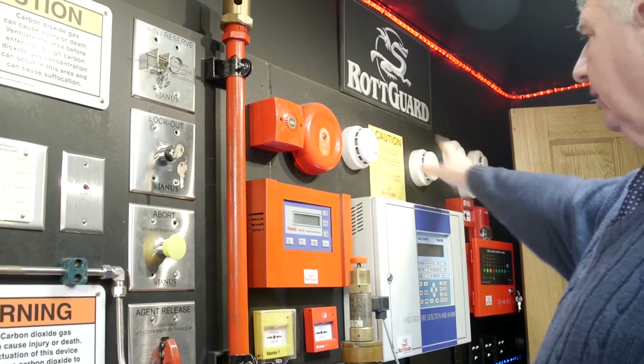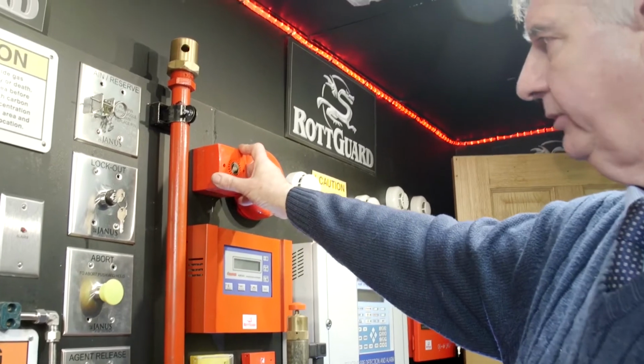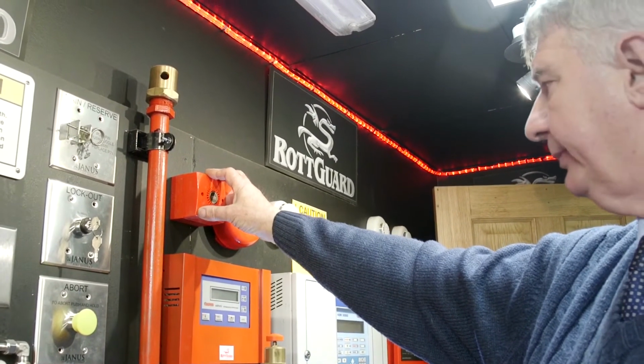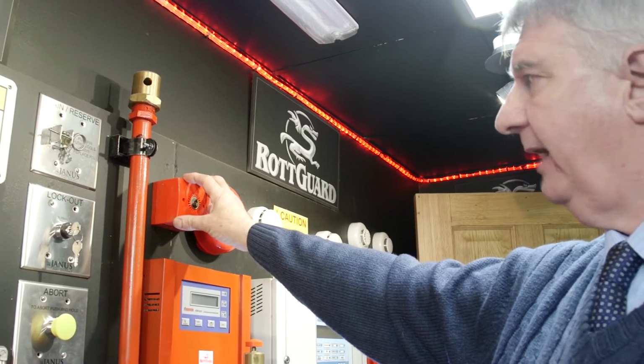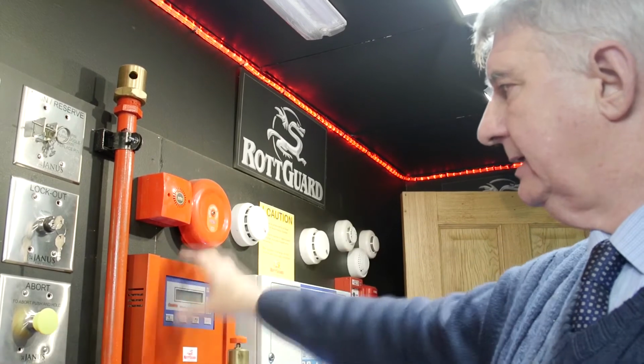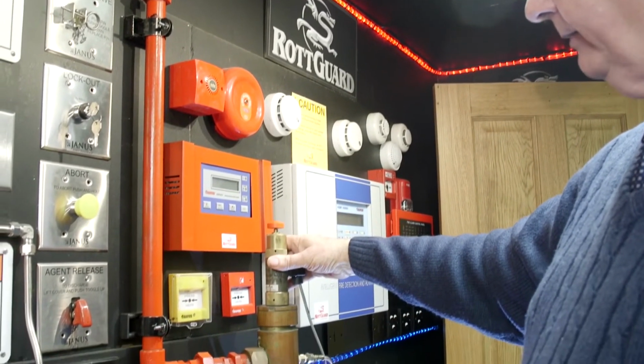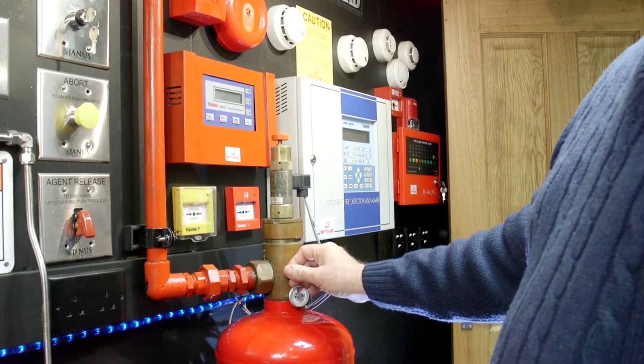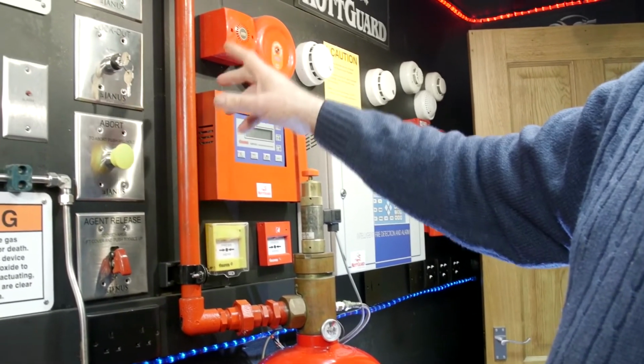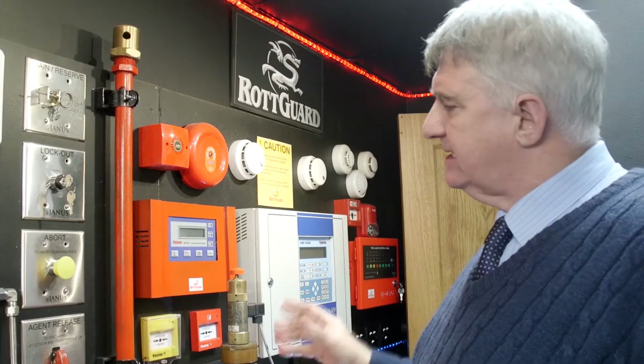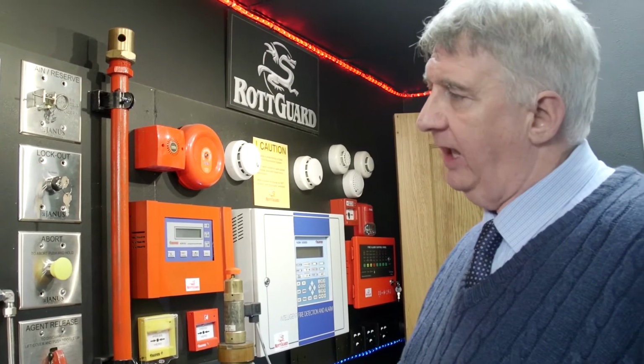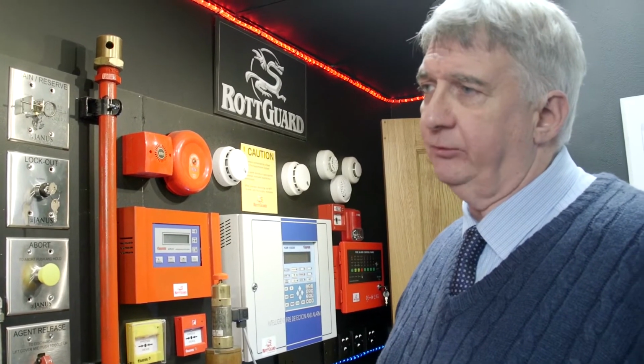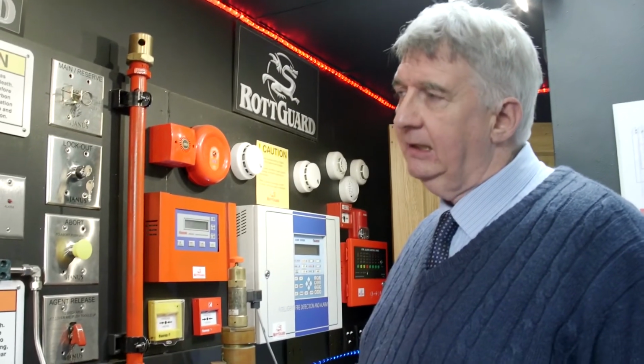Only if a second detector goes off will it trigger a second stage sounder, which oftentimes has a strobe light incorporated into it. 30 seconds generally after the second stage sounder is activated, this panel will send a signal to this solenoid to energize, thereby opening the valve on the cylinder, and the gas is discharged out through the discharge pipe. These systems commonly are designed to have 7% concentration in the protected room in the event of a discharge. To ensure that the room has the capacity to retain the extinguishing agent at the design concentration, it's necessary to do an integrity test on the room.